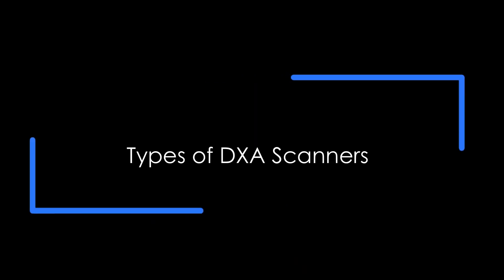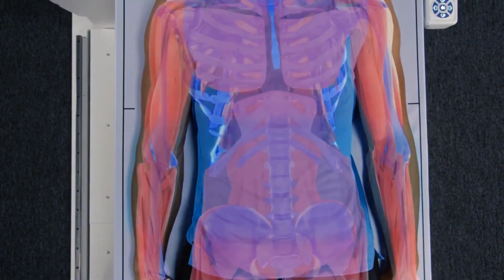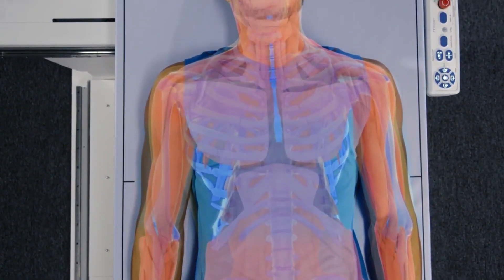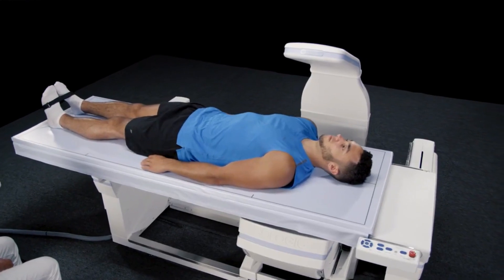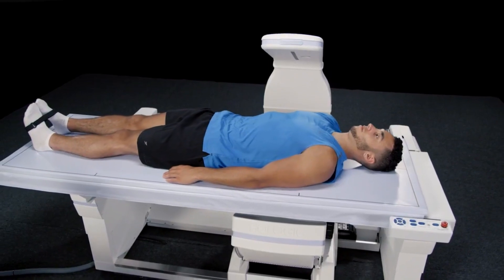Let's look into types of DXA scanners. There are two types of DXA equipment, a central device and a peripheral device. Most of the devices used for DXA are central devices, which are used to measure bone density in the hip and spine. They are usually located in hospitals' radiology departments.